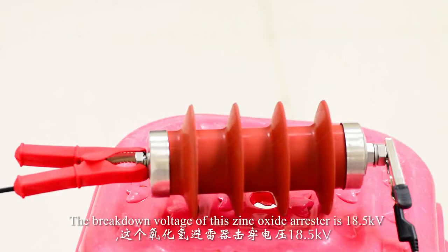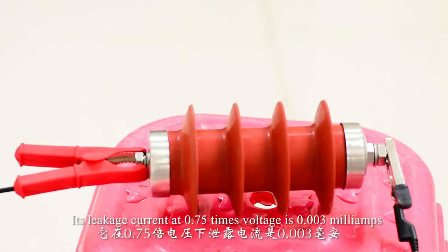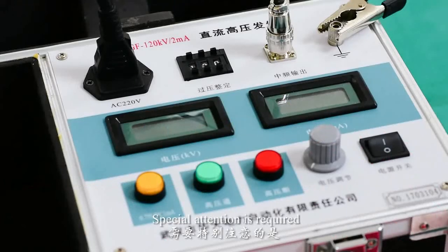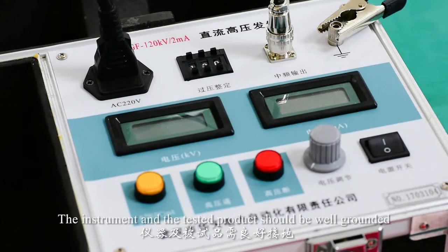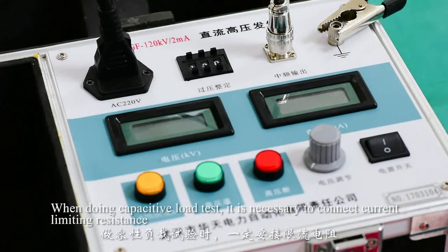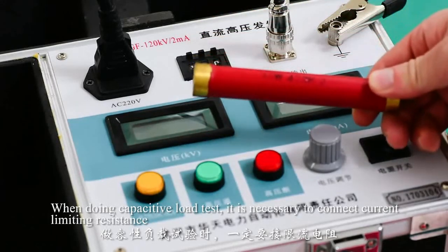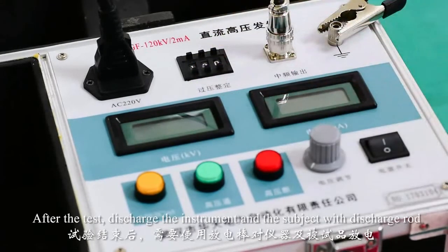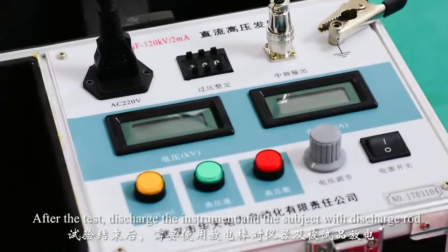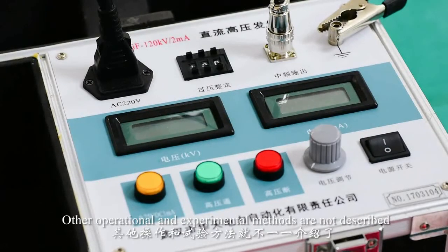The breakdown voltage of this zinc oxide arrestor is 18.5 kV. Its leakage current at 0.75 times voltage is 0.003 mA. Special attention is required. The instrument and the tested product should be well grounded. When doing a capacitive load test, it is necessary to connect a current limiting resistance. After the test, discharge the instrument and the tested load. Other operational and experimental methods are not described.